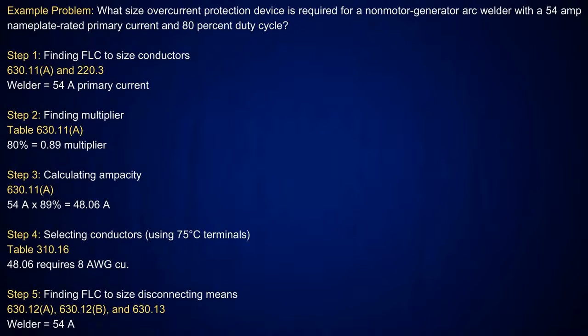And if you look at the overcurrent device, just to get people in the right direction to start off, I pick up 630.12a. It tells you should have an overcurrent device rated or set, and listen to what it says one more time, at not more than 200%. So that, once again, you can't exceed it because it says not more. So here's another high percentage where we're doing what? Dropping down to the next standard size.